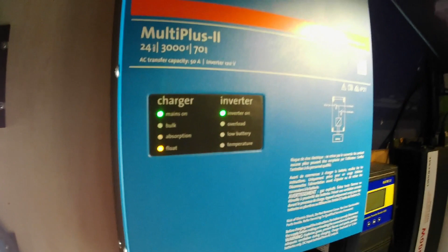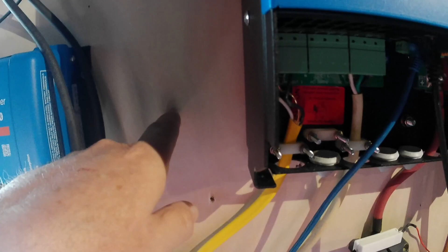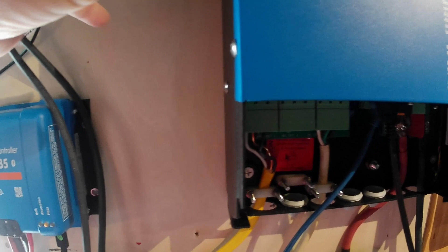So I'm going to have to run a sub panel in here at 50 amps. I'm going to give this Multi Plus 50 amps to be able to pass through it, so it can transfer that 50 amps out into this plug here. The plug I'm using will only be a 20 amp plug, but the output will then go into another breaker panel with a row of 20 amp and 15 amp breakers. That'll be my critical loads panel, as they call it.